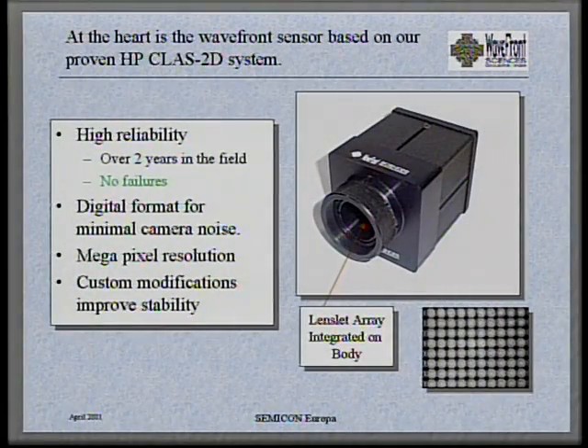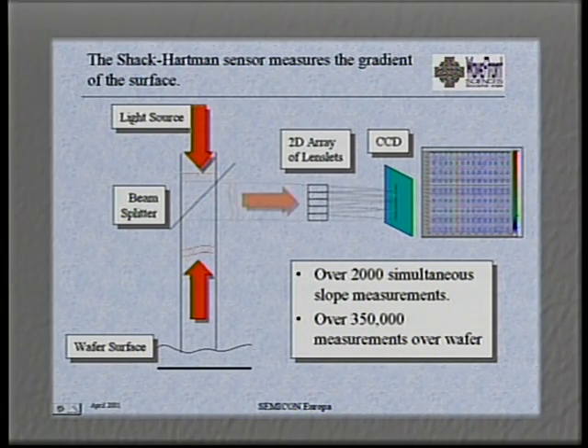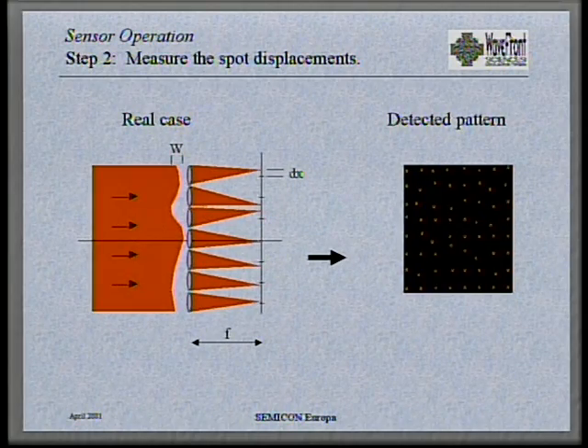At the heart of all Wavefront Sciences instruments is the Shack-Hartmann Sensor. When a beam of light is reflected from a surface or travels through an optical system, the resulting wavefront contains the imprint of the surface quality or optical characteristics of the object being tested. The Shack-Hartmann Wavefront Sensor divides this light into thousands of measurements and analyzes the imprint, which is a unique measurement, much like a fingerprint.